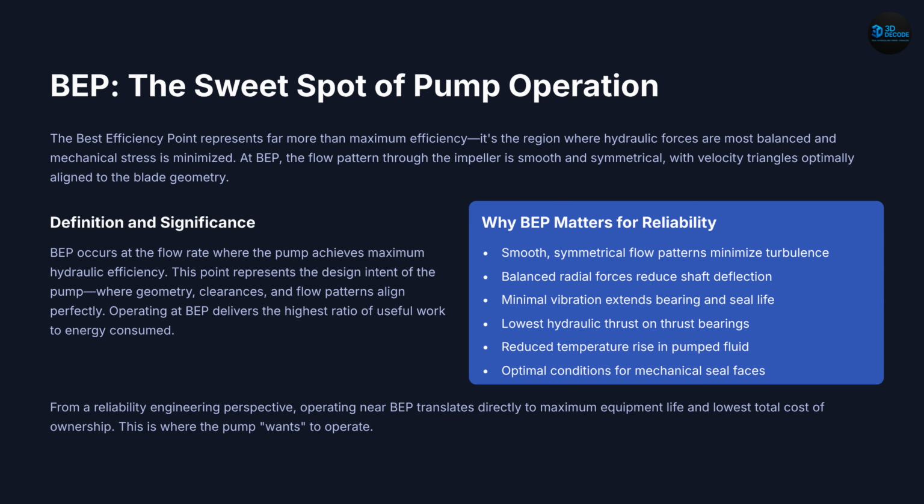Slide 3. The sweet spot. The best efficiency point is where the pump operates at maximum efficiency. But more importantly, it is where hydraulic forces are balanced. Flow is smooth, vibration is minimal, and mechanical stress is lowest. This is the condition where the pump wants to operate.